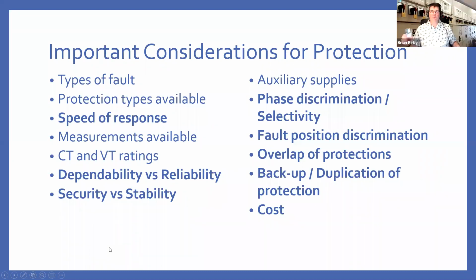So here's a list of important considerations. And I've selected a few in bold, which are things that you have more control over as a protection engineer. Types of fault. Typically, the type of fault is dependent on the system that you're protecting, so you can't really control that. Similarly, types of protection available. Today, there are lots of different protection schemes available, and typically they're all available in a common form factor. A single device normally will do most of your protection functions. Speed of response is something you will be able to influence. This is important if you've got sequential protection schemes. The available measurements and CT and VT ratings may be under your control, but typically they're not.